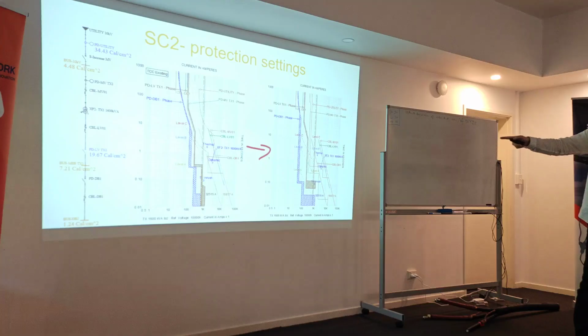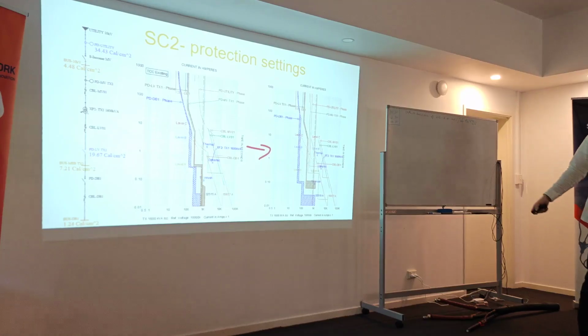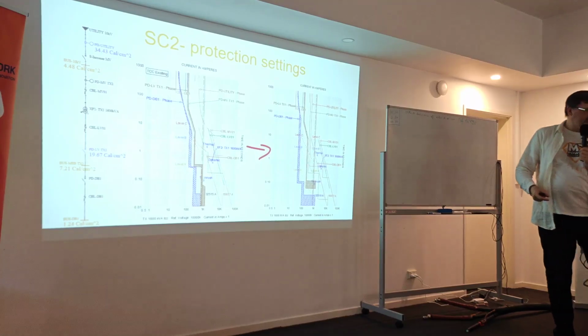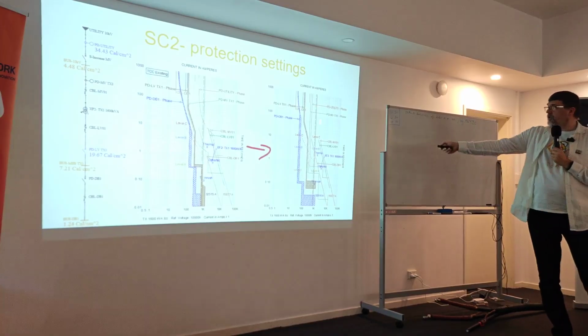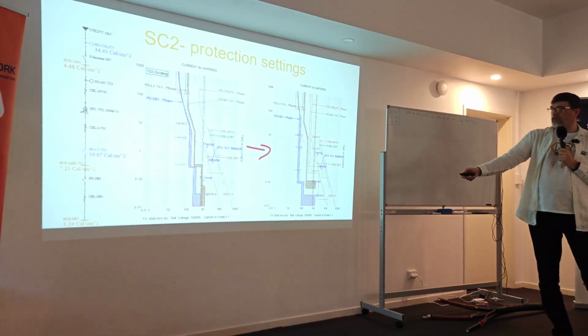But if you look, it wasn't that smart a relay, because technically it has a 1, 2, that's it. Normally, if the relay is smarter and allows you to make 3 groups or 3 or 4 steps of settings, then I will probably keep this inverse time like they have, because it technically was possible. Keep it and then drop it and then go. But this relay was not that smart at some point. But technically we can do it because we have a low voltage breaker that will protect from overload.